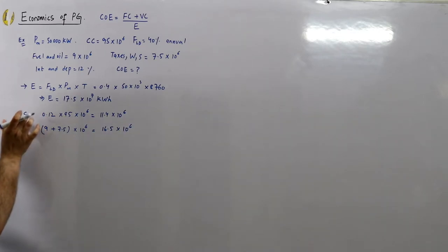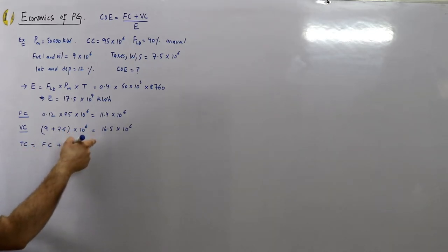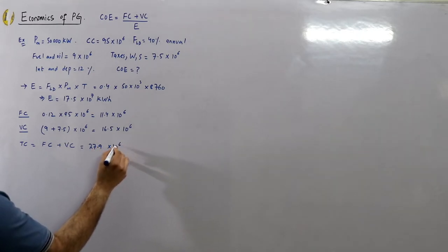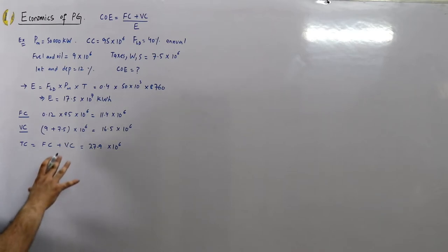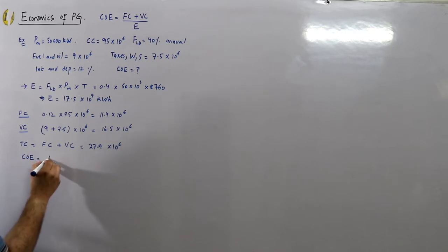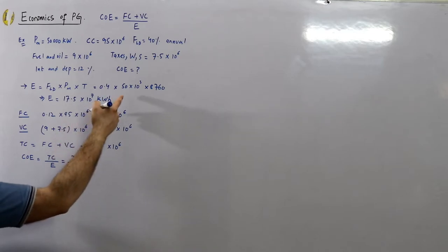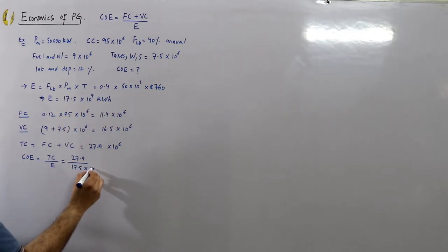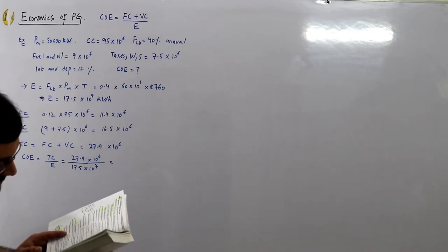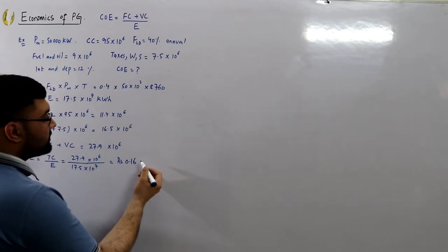Total cost = fixed charges + variable charges = 11.4 + 16.5 = 27.9 × 10⁶ rupees. The cost of electrical energy per unit = total cost ÷ energy units = 27.9 × 10⁶ ÷ 17.52 × 10⁷ = rupees 0.16, or 16 paise per unit.